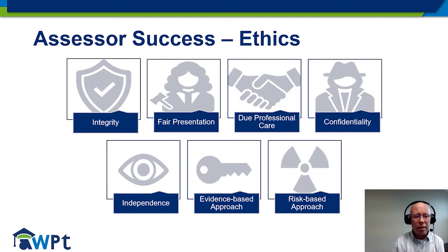Okay, making sure that there's independence where it's possible. 17025, even for a one-person laboratory, doesn't really talk about internal auditing of yourself, because you can't do it. The only place it talks about going outside of yourself is when dealing with complaints, where at some part of it you have to bring somebody else in to manage it if the risk is significant enough. And I would encourage you to read section 7.9 on that.